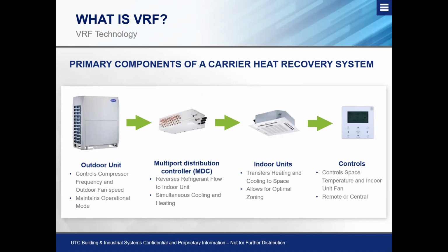So when we talk about differences, the creation of three states of refrigerant just happens in different places. On the Carrier two-pipe system, it happens in what we see on our screen here as our MDC. On the Toshiba Carrier system, it happens in the outdoor unit, which is why we have a three-pipe heat recovery system there, and why we can have a two-pipe heat recovery system on our Carrier VRF outdoor. Okay, it's just a little bit confusing. There definitely are some intricacies in understanding what is heat recovery and what isn't. But in a basic nutshell, this is pretty much what we're working with as far as a Carrier heat recovery system is concerned.